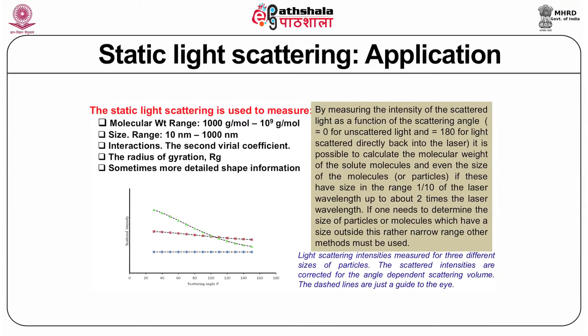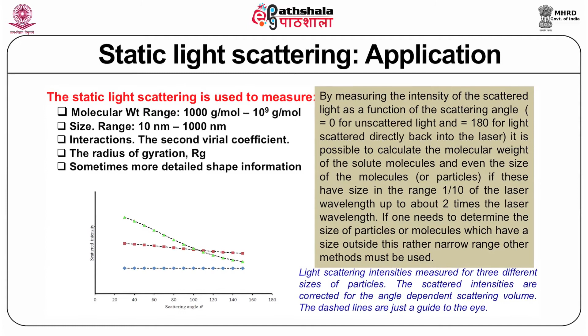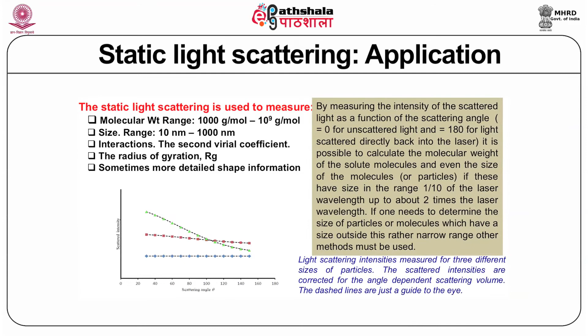By measuring the intensity of scattered light as a function of scattering angle theta, for unscattered light and at 180 degrees for the light scattered directly back to the laser, it is possible to calculate the molecular weight of the solute molecules and even the size of the molecules or particles if these have a size in the range of 1 by 10 of the laser wavelength up to about 2 times the laser wavelength. If one needs to determine the size of particles or molecules which have a size outside this rather narrow range, other methods may be used. Light scattering intensity measured for 3 different sizes of particles. The scatter intensities are corrected for the angle dependent scattering volume, and the dashed lines are just guidelines.